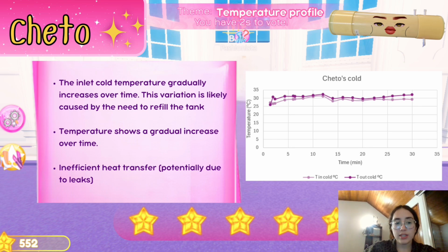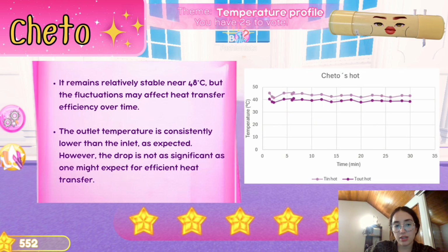For the hot fluid, the inlet temperature fluctuates slightly for the same reason as the cold fluid, the tank refilling, and stabilizes near 48 degrees. The outlet temperature is consistently lower than the inlet, as expected. However, the drop is not as significant as one might expect for heat transfer. The hot fluid outlet temperature stabilizes around 42 to 43 Celsius, indicating heat loss potentially affected by the leaks.